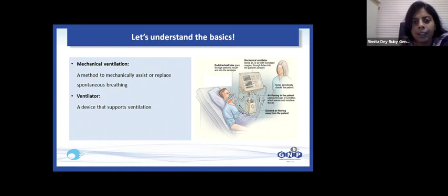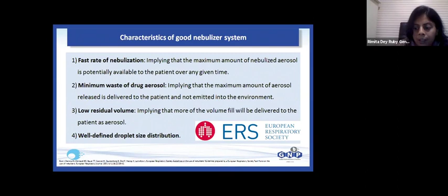Now, the characteristics of a good nebulizer system, if you want to understand, are a fast rate of nebulization, implying that the maximum amount of nebulized aerosol is potentially available to the patient over any given amount of time. There should be minimum wastage of the aerosol, implying that the maximum amount of aerosol is delivered to the patient and is not emitted to the environment. There should be low residual volume, implying that more of the fill volume will be delivered to the patient per aerosol delivery. And there should be a well-defined droplet size distribution. I'll tell you about the size of the droplets which are actually important for drug delivery.